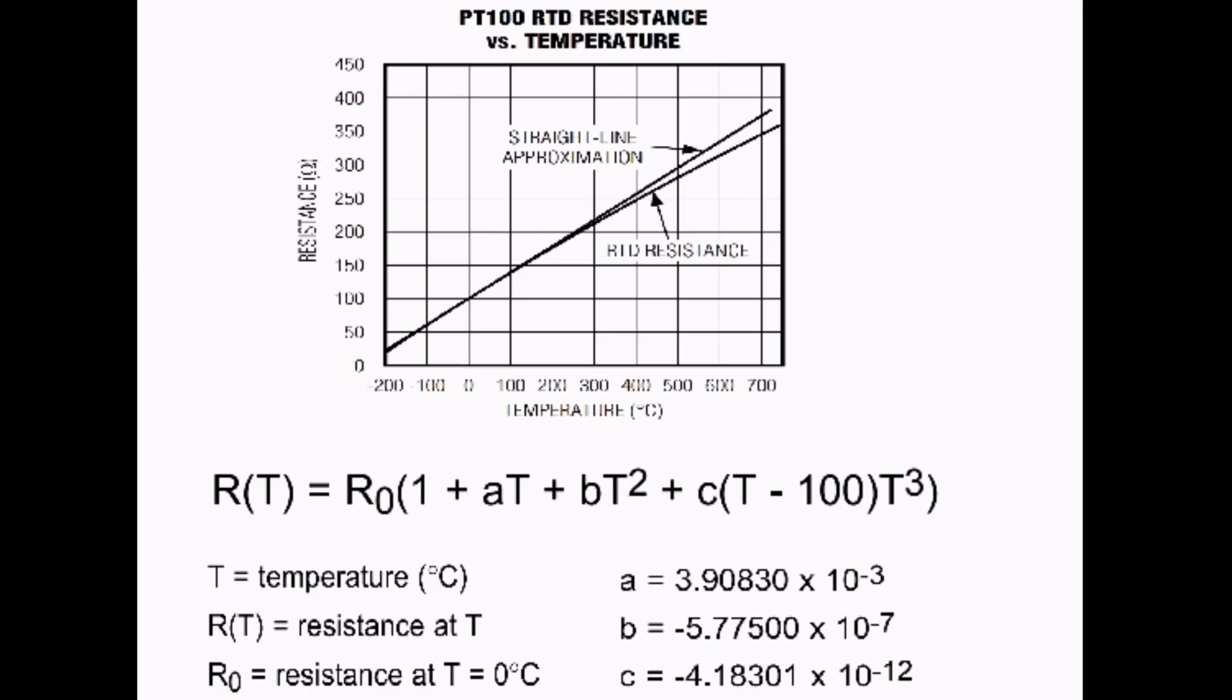One last topic I'd like to cover before doing our demo is the Callendar-Van Dusen equation. This equation describes the correlation between temperature and resistance of the RTD. We can see here the curve for a PT100 is relatively linear, but does have some curvature.